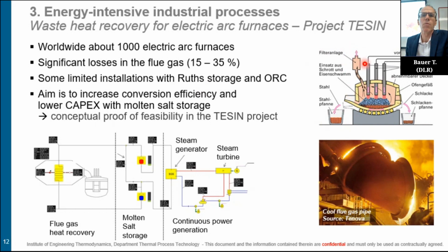And the typical way is they don't use the heat in the flue gas at all, and the heat in the flue gas is between 15 and 35% of the heat input. A typical furnace maybe has 100 megawatt of electrical power. So you can imagine that you have a lot of flue gas heat here. There are some limited installations of Ruths storage systems. So what they do, you can see a picture at the bottom, is install a heat exchanger in the flue gas stream here. This is a heat exchanger with direct steam generation. And then they inject it into a Ruths storage system, and they couple this with an ORC process. But this process is not very efficient. It's expensive, the ORC. The Ruths storage has a decline, so you don't have a constant temperature outlet of the Ruths storage. So this is not an ideal solution.